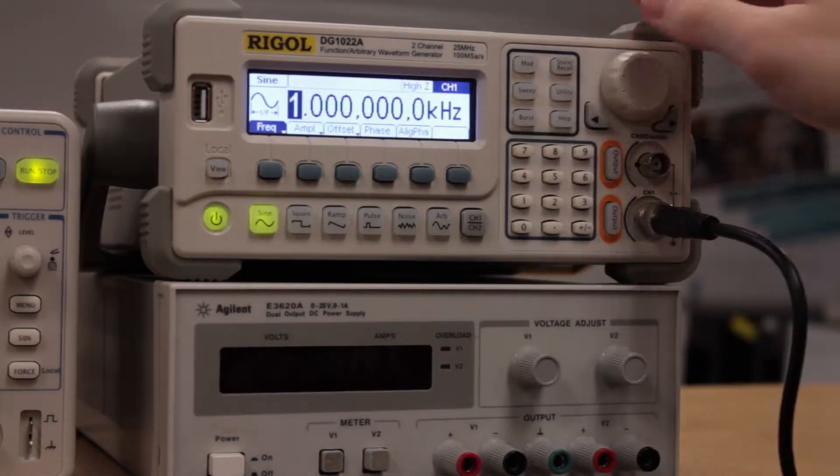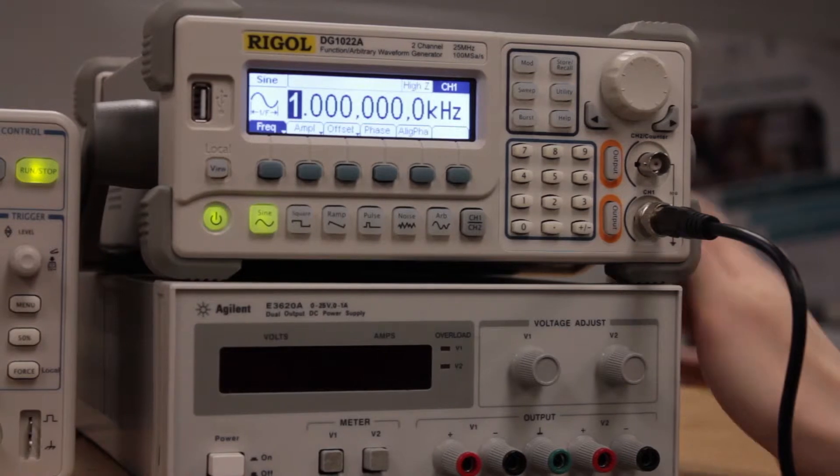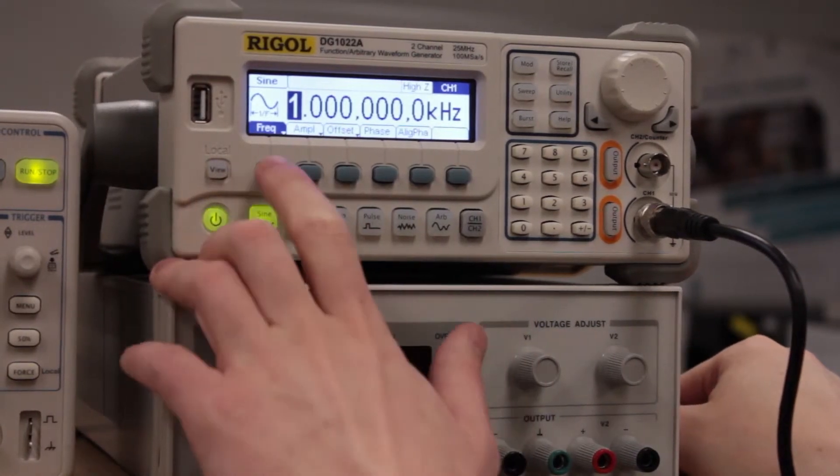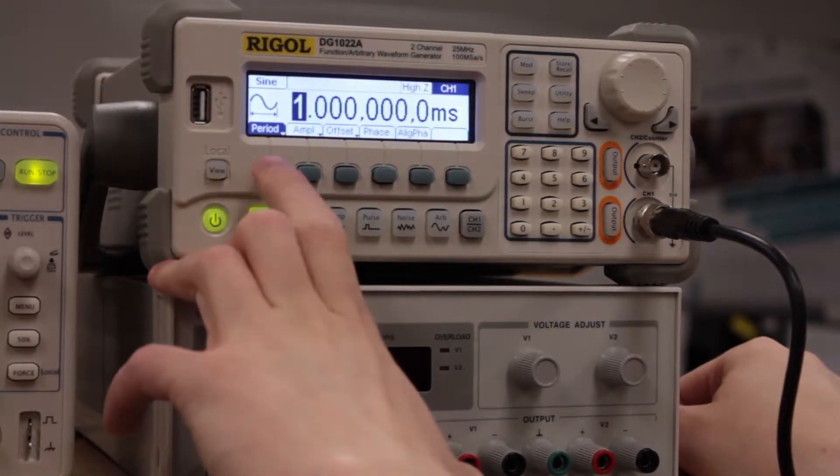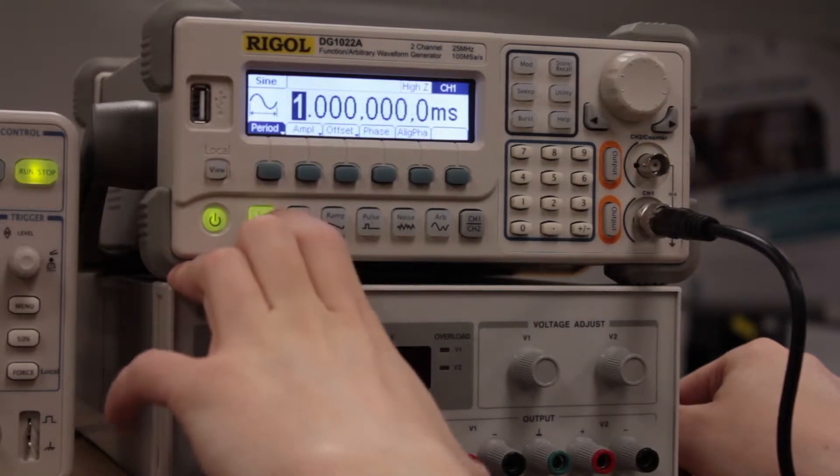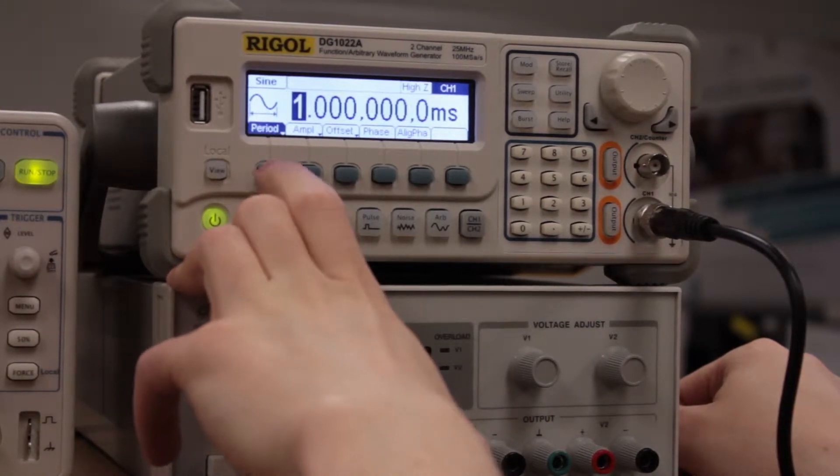One of the things that messes people up is if you hit this, you can set the period. A lot of times it'll boot up and it'll be in frequency, for example, and you'll want to set a specific period. This is how you do it - you just hit this button and it switches between the two.